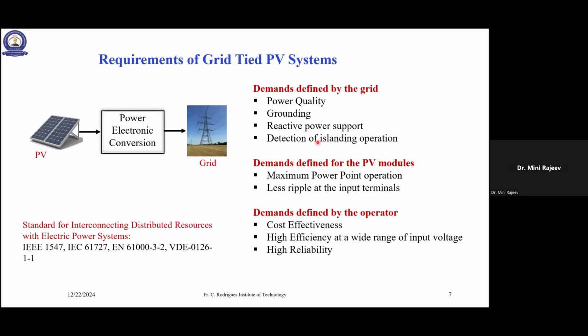You know what is islanding operation? Anyone? What do you mean by islanding operation? Any idea? Ma'am, when we will not connect our consuming part to the grid, and it will be separate, completely separate. That's the system said the island. Actually, I know it's something related, but suppose the grid fails, but your inverter will still be supplying to some section of the grid. So that is what you mean to say by islanding operation.